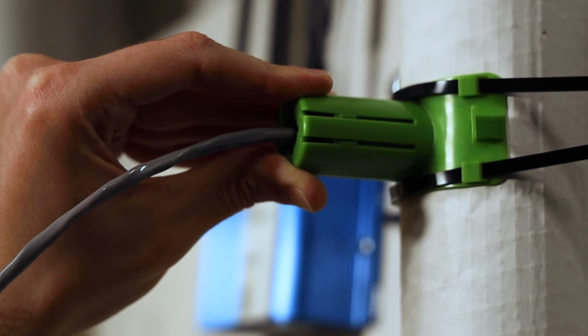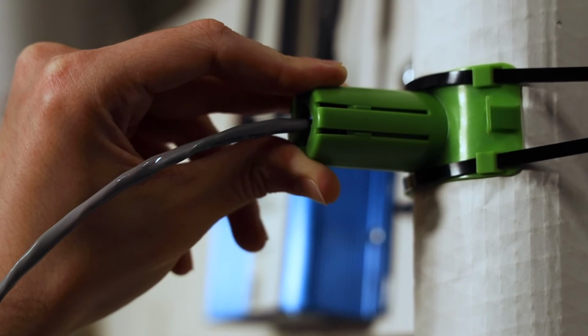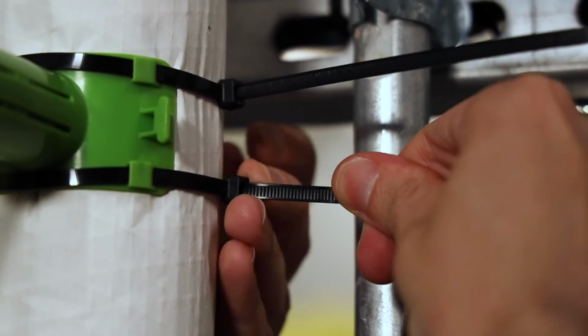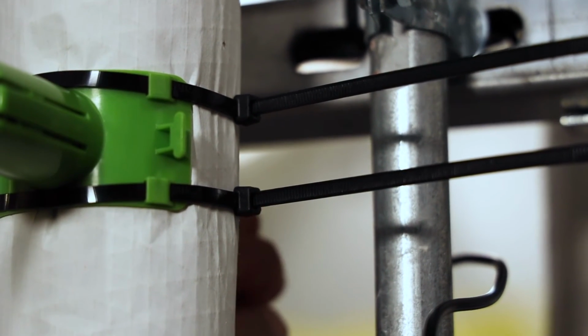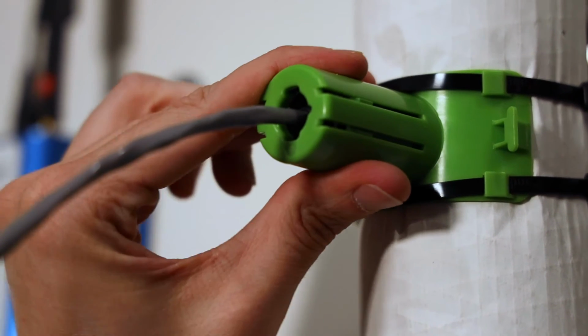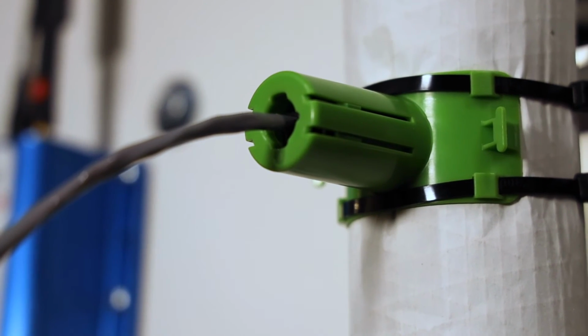The assembly is spring-loaded to keep the sensor probe in firm contact with the pipe. Snug up the cable ties evenly so the sensor sits against the insulation and stands completely perpendicular to the pipe. Make sure it's not angled or sagging.